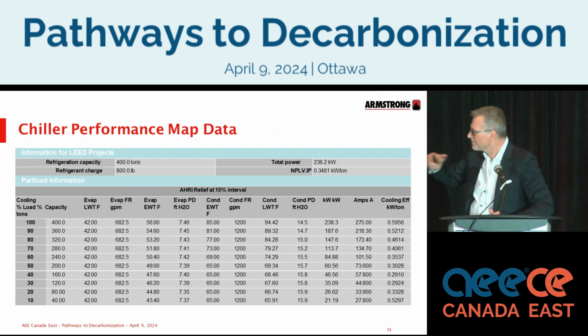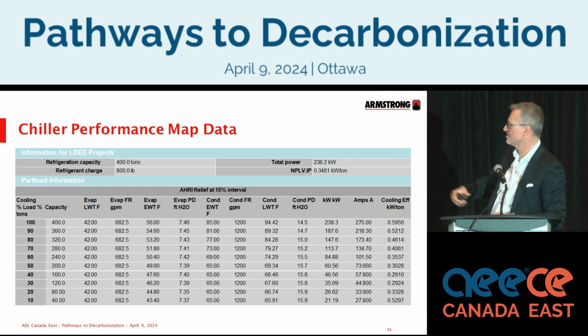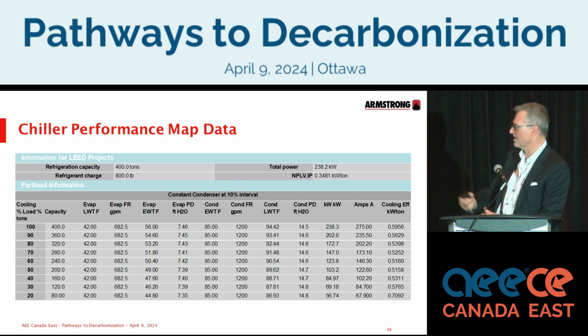And I like bringing up the performance maps here. This map is based on 10% intervals on AHRI relief. So, if we're looking at condenser water temperatures anywhere from 94 to 74, you'll have your kilowatts per ton anywhere from 0.596 at 100% down to about 0.30 at 50%. And then conversely, if we're looking at constant condenser temperature, again, even at constant condenser temperature, at 100%, you're at 0.59. At 50%, you're at 0.51.